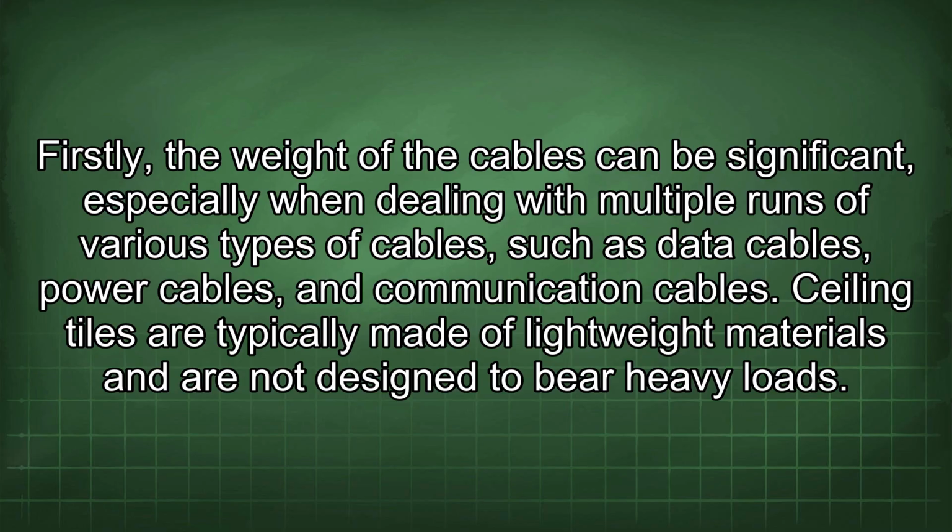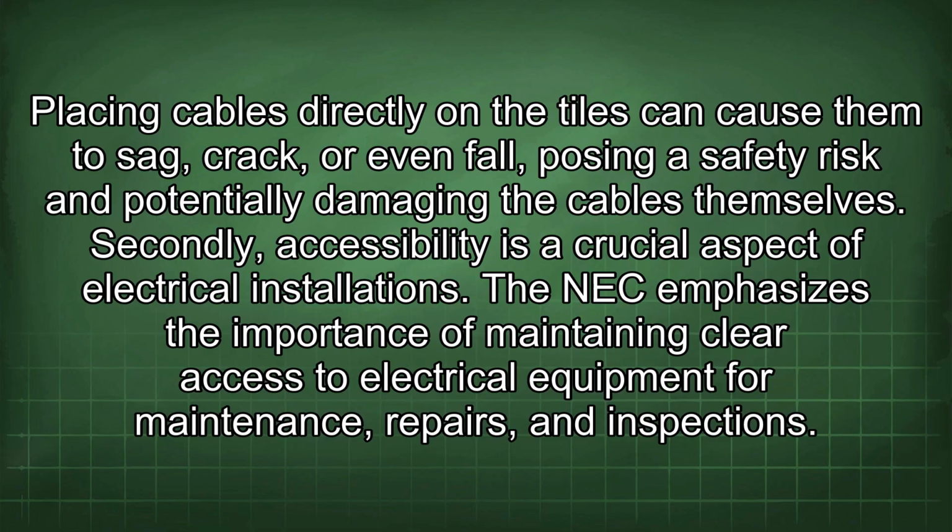Firstly, the weight of the cables can be significant, especially when dealing with multiple runs of various types of cables, such as data cables, power cables, and communication cables. Ceiling tiles are typically made of lightweight materials and are not designed to bear heavy loads. Placing cables directly on the tiles can cause them to sag, crack, or even fall, posing a safety risk and potentially damaging the cables themselves.